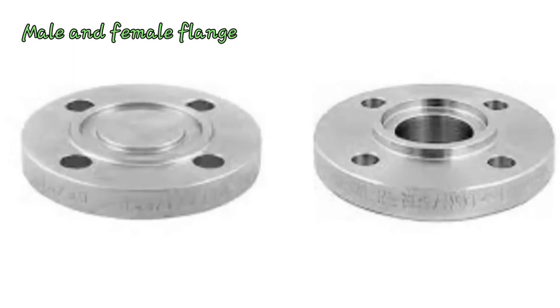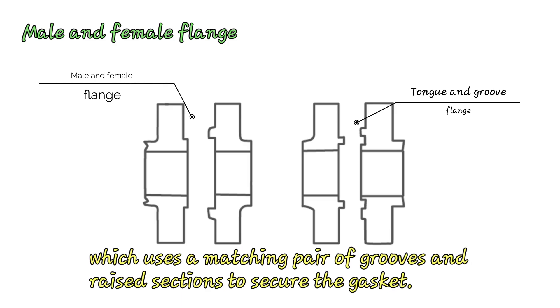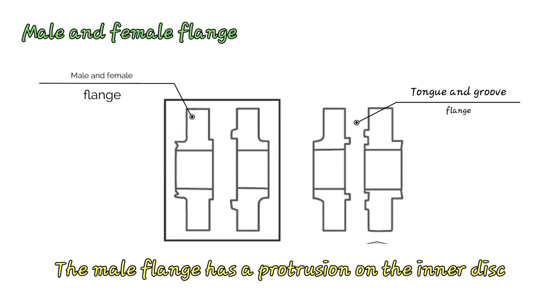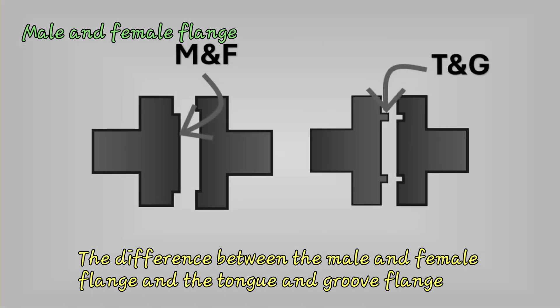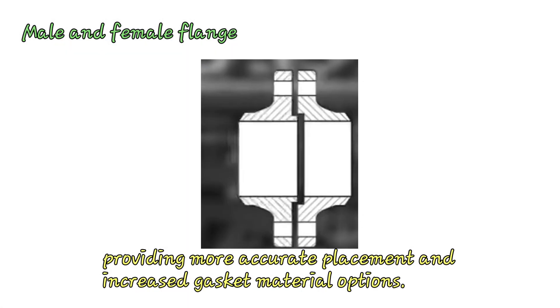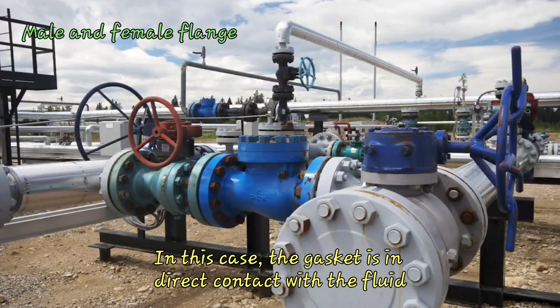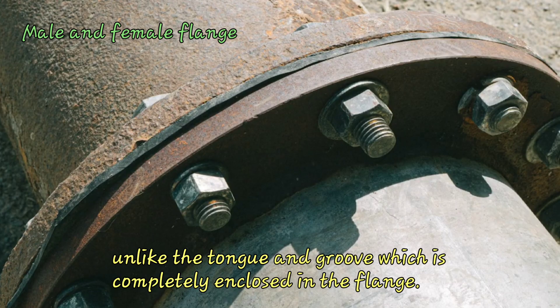The male and female flange is similar to the tongue and groove flange, using a matching pair of grooves and a raised section to secure the gasket. The male flange has a protrusion on the inner disc while the female has an indentation on its inner face. The difference is that the male and female flange retains the gasket on the female face, providing more accurate placement and increased gasket material options. In this case, the gasket is in direct contact with the fluid, unlike the tongue and groove which is completely enclosed in the flange.